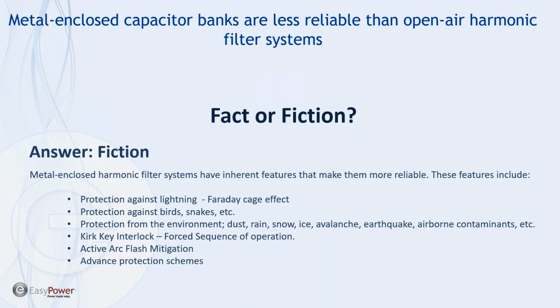In addition, the metal-enclosed system had other benefits from a reliability standpoint. The enclosure itself protects the internal components from lightning, Faraday cage effect. The enclosure protects against birds and snakes and wildlife, so there's a prevention for flashover within the enclosure. We also protect the internal components from dust, rain, snow, ice. We've done avalanche designs, earthquake, we're a seismic 4 zone, and then airborne contaminants. We can protect the internal components, those energized live parts, from those contaminants.